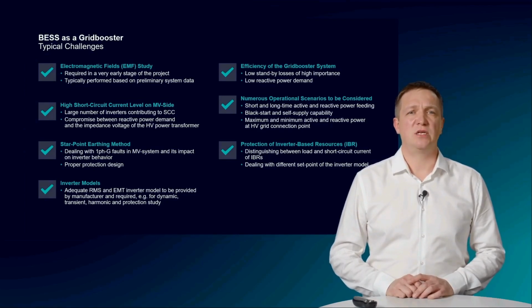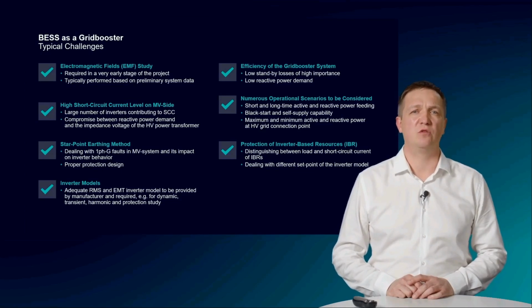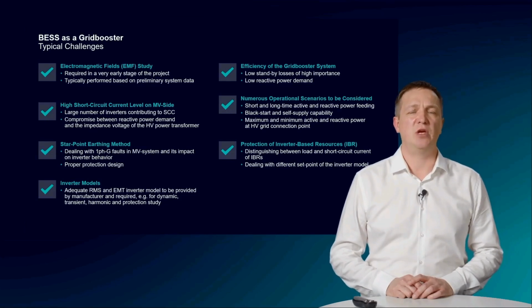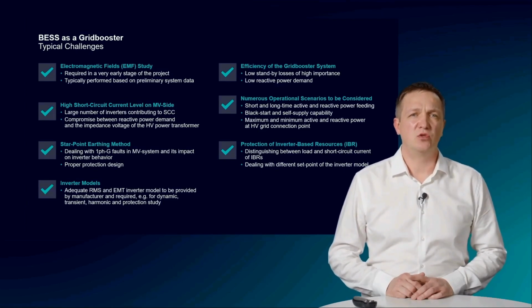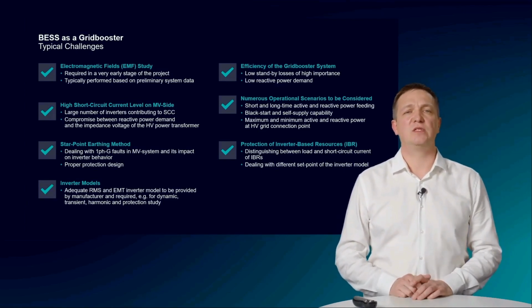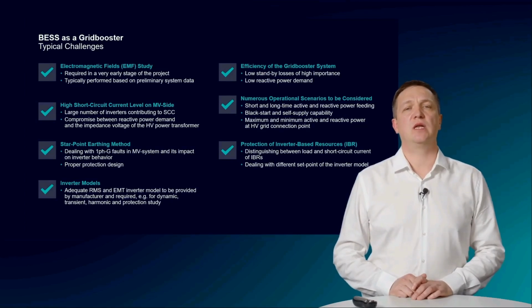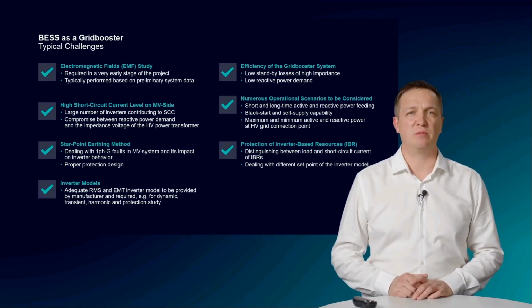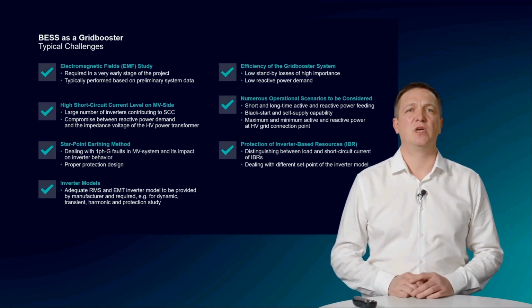The next challenge is the selection of the most advantageous star-point earthing method for the medium voltage system. This selection has an impact especially on the operational philosophy of the grid booster, namely on dealing with single phase-to-ground faults, and on the protection concept. When deciding on a neutral grounding transformer, the single phase-to-ground faults are limited to a certain level, for instance 500 amps. This allows the reliable detection and isolation of the faulty equipment.